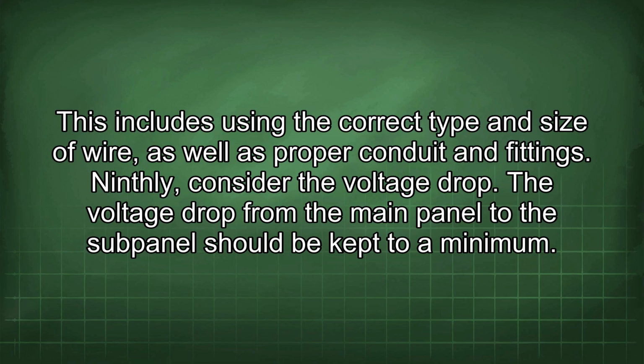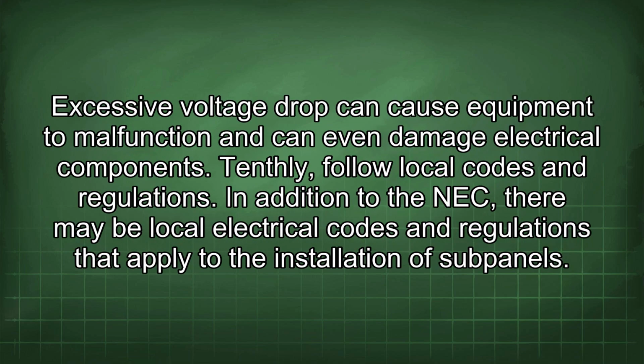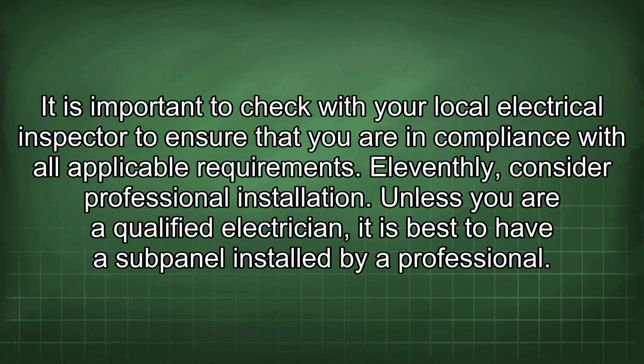Ninthly, consider the voltage drop. The voltage drop from the main panel to the subpanel should be kept to a minimum. Excessive voltage drop can cause equipment to malfunction and can even damage electrical components. Tenthly, follow local codes and regulations. In addition to the NEC, there may be local electrical codes and regulations that apply to the installation of subpanels. It is important to check with your local electrical inspector to ensure that you are in compliance with all applicable requirements. 11thly, consider professional installation.